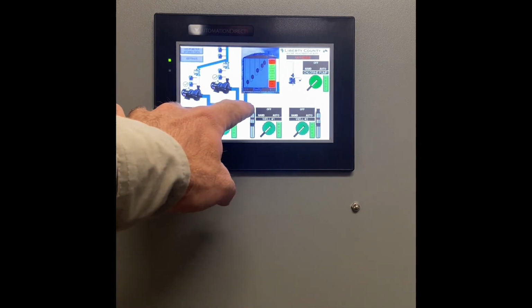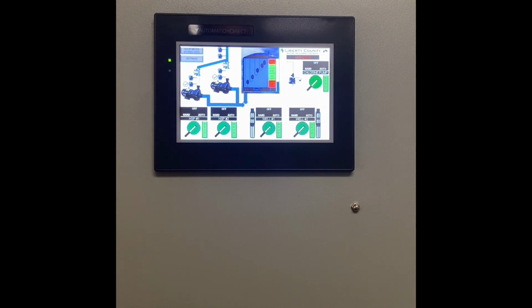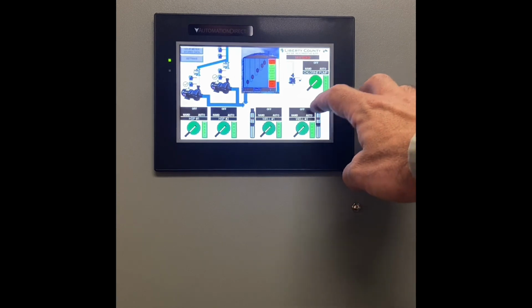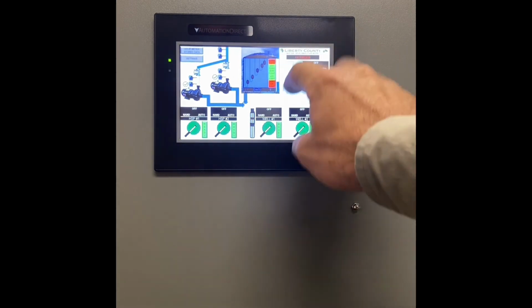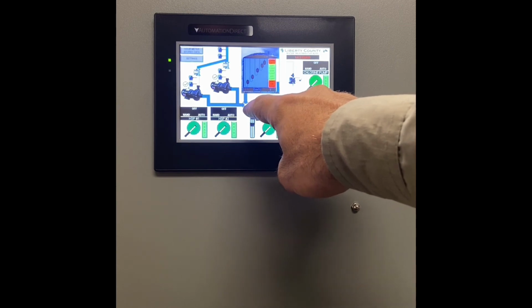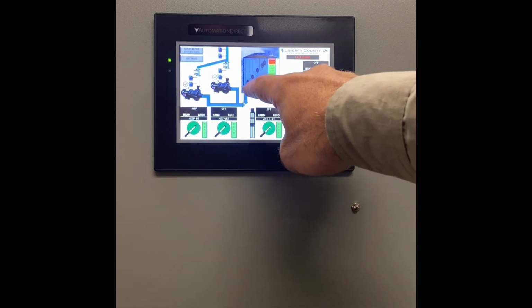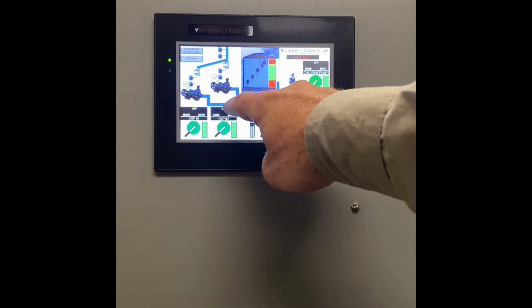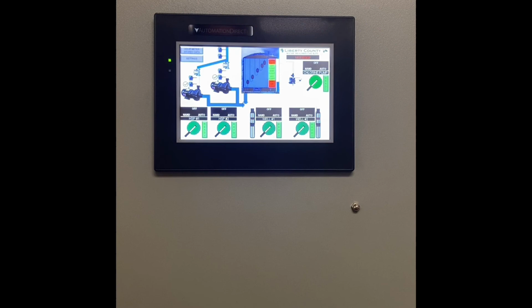Now, you'll notice that we have a valve indicator here of a 3-way valve. That valve is not anywhere in the system mechanically. It is merely a representation of the realignment of how the system will function if the groundwater storage tank is put in bypass. Right now, the system is being shown to be in normal. The piping leaving the well motors and coming up is going over to the groundwater storage tank, and you notice that that port on the valve is now white, where the pipe coming out of the storage tank is blue, and the indication leaving the valve going to the high service pumps is also blue to tell you which way the water will flow.